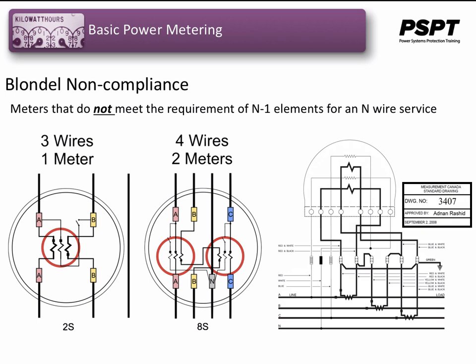Here are some examples of meters that are not Blondel compliant. Going from left to right, there are 3 wires in this system, but they're only using 1 element to meter the system. And in the middle one, there are 4 wires, and they're only using 2 elements to meter the system. And in the case of Measurement Canada Standard 3407, they assume that the voltage vectors or phasors are equal and 120 degrees apart. So making that assumption doesn't introduce a great deal of inaccuracy into the metering system, as long as you can sum the currents, which they can do here in the case of using CTs. So they can get away with using a 2-element meter, and they do it quite often. And this ends chapter 6.